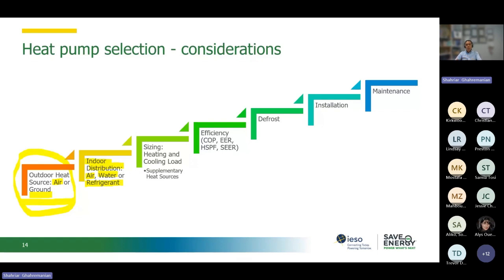If it's a brand new building, it's better that we think of the indoor distribution system as well. As you know, air has a lower heat capacity compared to water, and water has a lower heat capacity compared to refrigerant. Water is 4 times better than air if we want to distribute heating or cooling. For conductivity, water has 25 times more heat conductivity compared to air. And refrigerant is much better than these two as well.